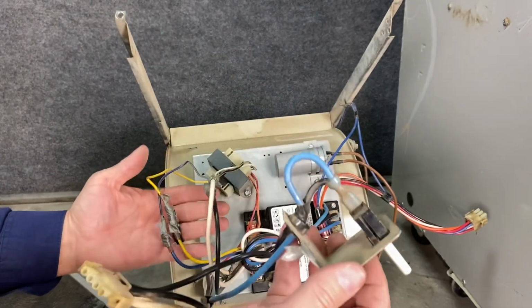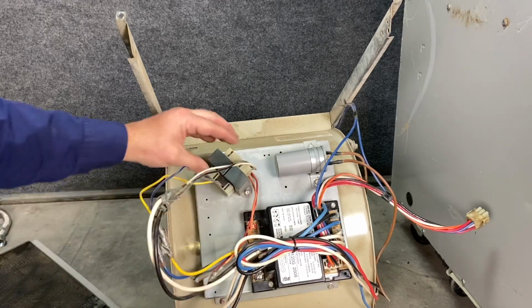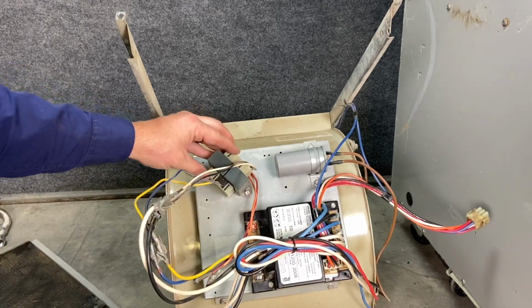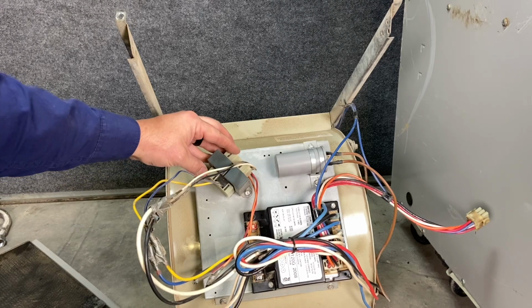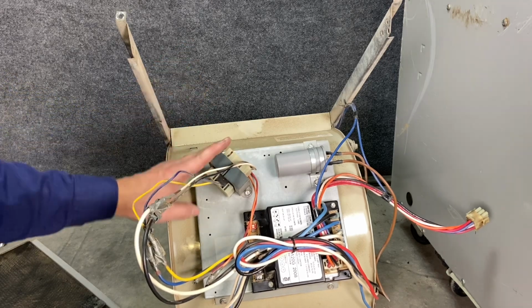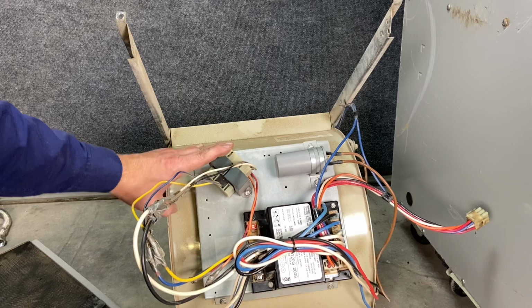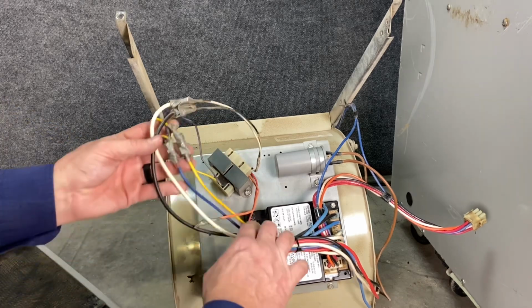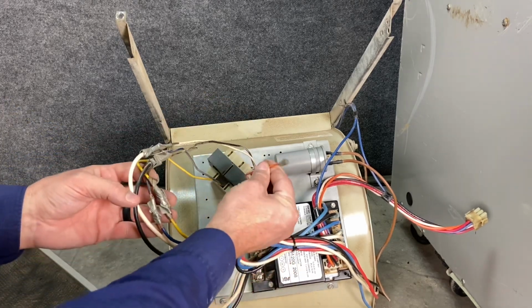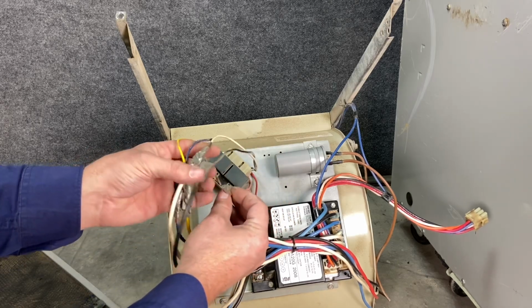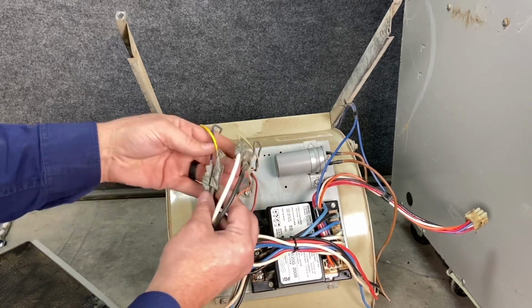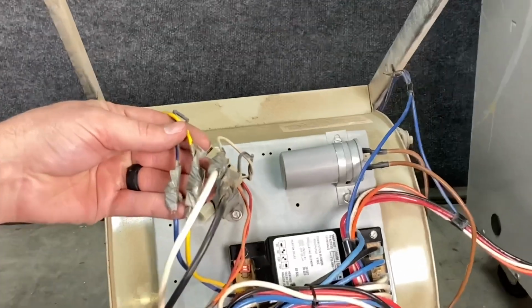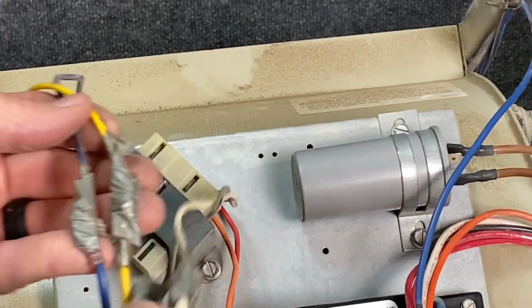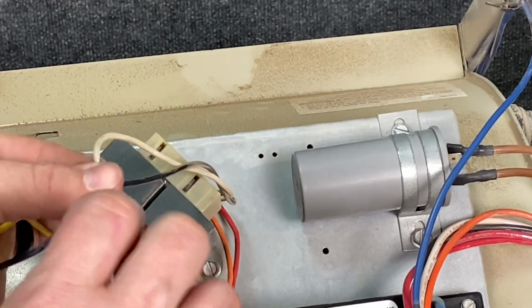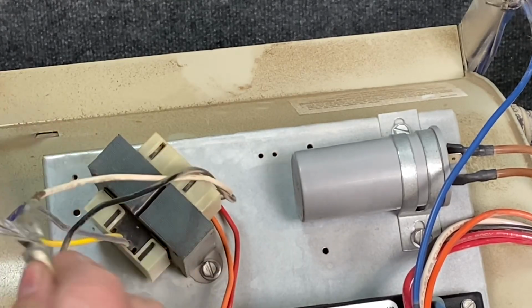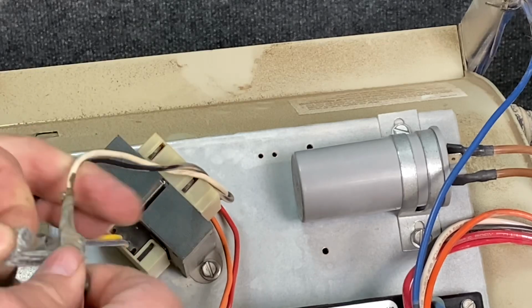It's simple to replace. Now, another thing I want to point out is our transformer. This transformer has been replaced, which means there was a short in the system at some point in time. A transformer never goes bad without a short, so something had to have shorted it out. So somebody's replaced this transformer, and it's a universal, which is why we have an extra wire. But what I see here is absolutely horrifying. There is duct tape used to hold these wires on. And that's right, duct tape. So I'm curious to see what's behind the duct tape, what kind of connection they used. So we're going to go ahead and pull these wires off, this tape off, and see what the wire looks like.